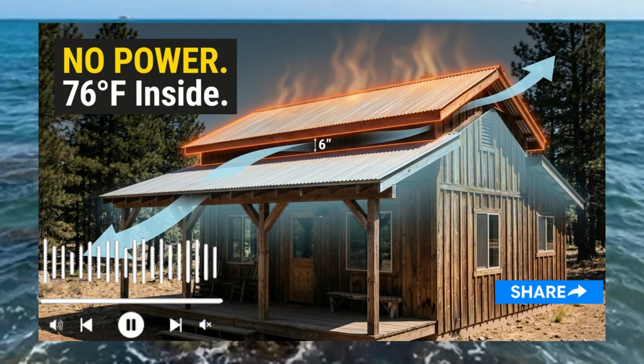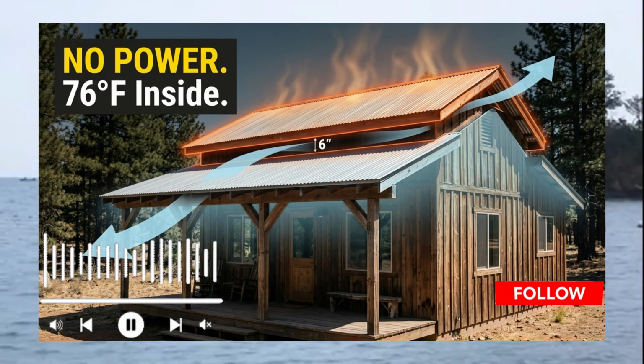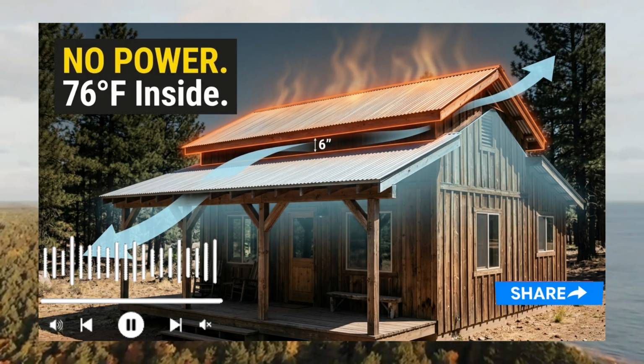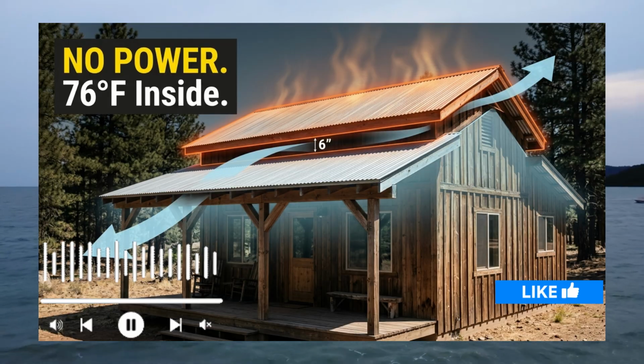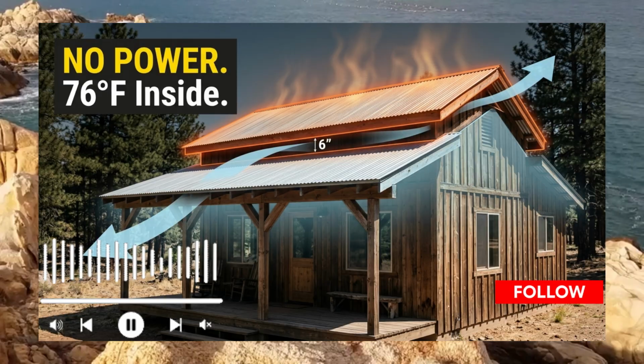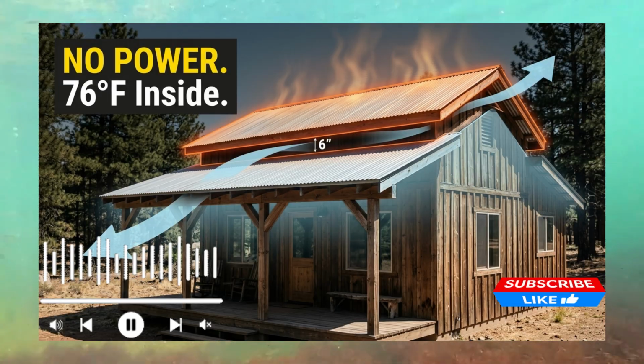The most dramatic data point appeared on the surface of the primary lower roof deck underneath the shade roof. While the outer skin boiled at nearly 160 degrees, the primary weather deck sitting in continuous shadow registered at just 98 degrees Fahrenheit.